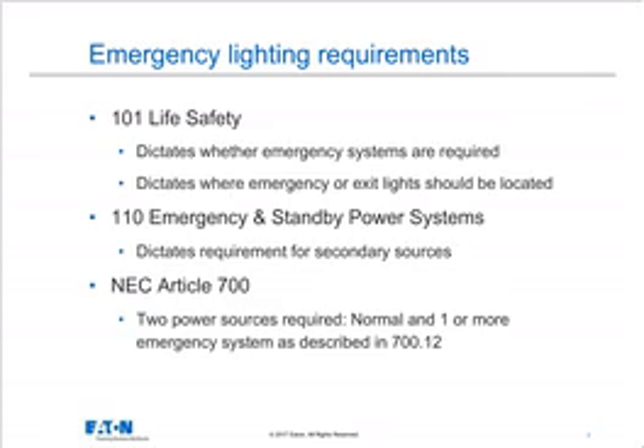Okay, emergency lighting requirements. NFPA 101 is concerned with life safety. What we're doing is making sure, primarily, that people can safely exit a building in a lighting or power emergency where it would otherwise be too dark to find your way out. So NFPA 101 dictates whether emergency systems are required, and where and how many emergency lights need to be located, and how much light in lumens needs to be provided in order to adequately light an egress path from a building.